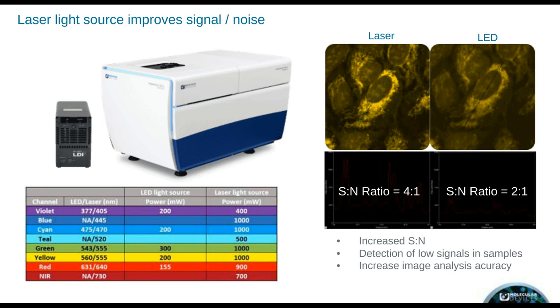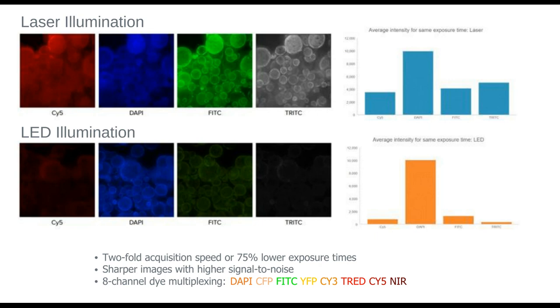Another relevant feature is the type of light source. Most recent versions of these instruments bring high-power eight-channel light sources — between two and six times more powerful than the previous generation. Using laser light sources of that nature brings increased signal-to-noise compared to LED illumination, allows detection of low-signal samples, and increases data accuracy. In practical terms, this means a twofold acquisition speed increase with up to 75% lower exposure times compared to LED illumination. You'll have sharper images and wider flexibility with eight channels allowing for multiplexing.